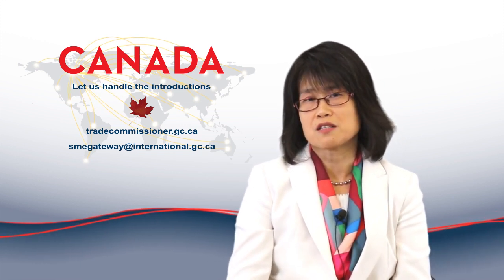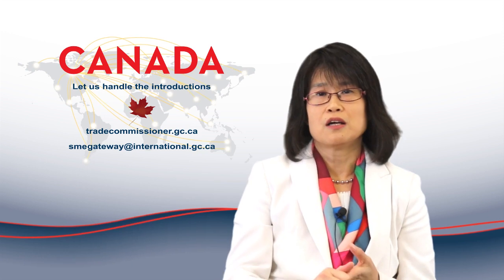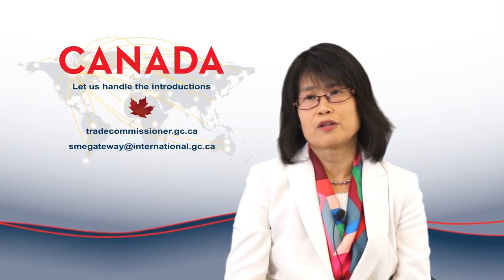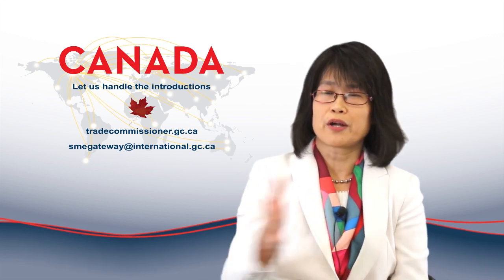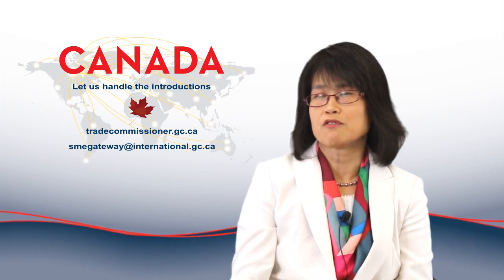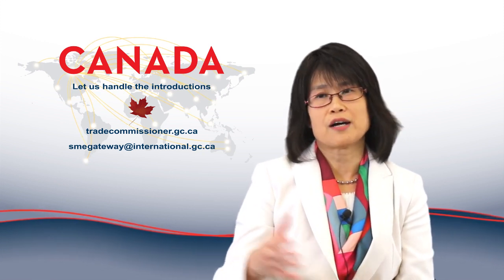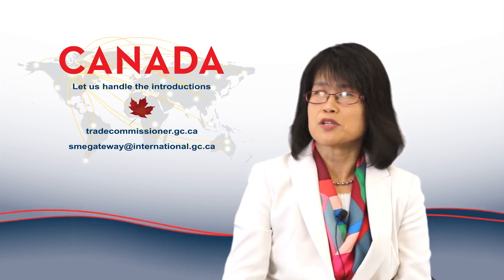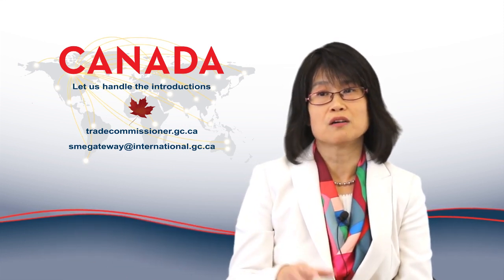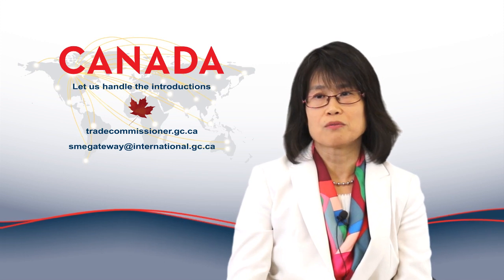From our company, I talk extensively with clients about their product, its application, and its classification in the US, EU, or Health Canada, and then we see how China matches this — an exact match, almost a match, or a contradiction. These issues must be handled prior to submission. This is the only way to go in with confidence that you have the right classification and requirements, because if the classification is wrong, your submission gets kicked out of CFDA right away and you start from zero again.